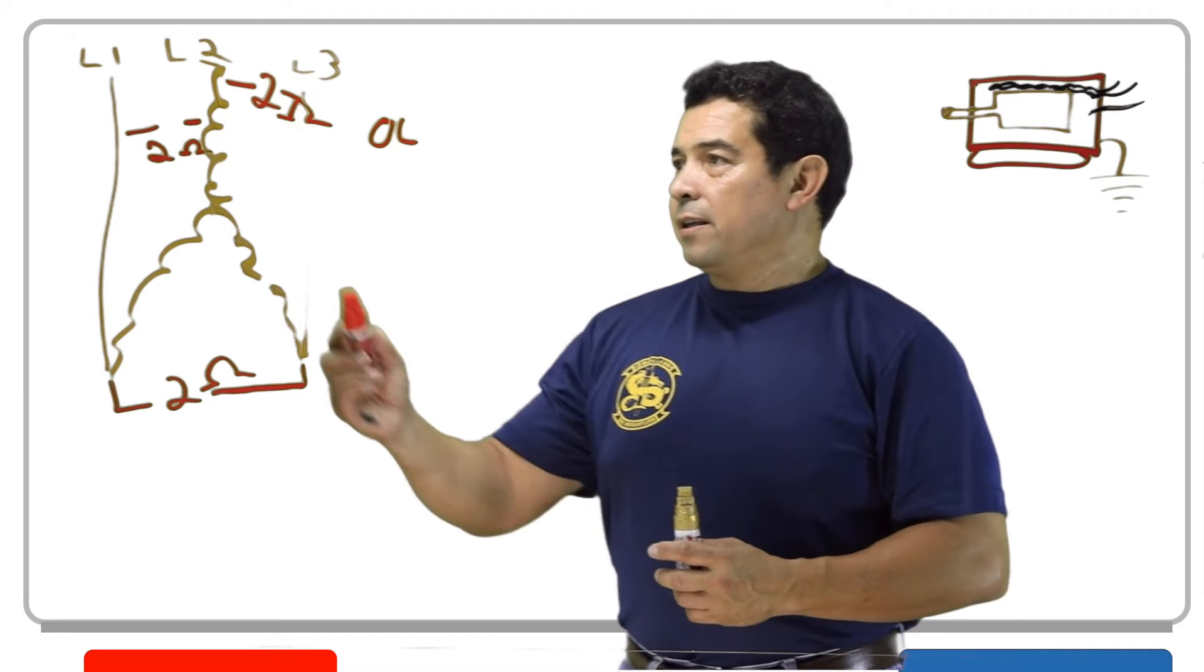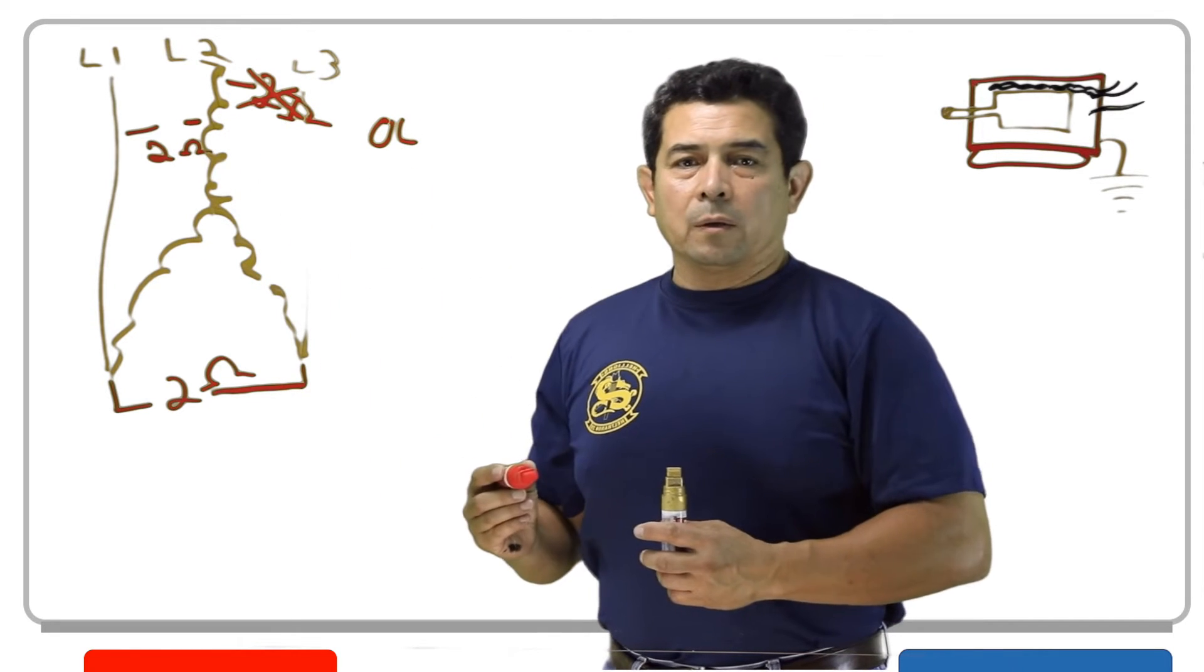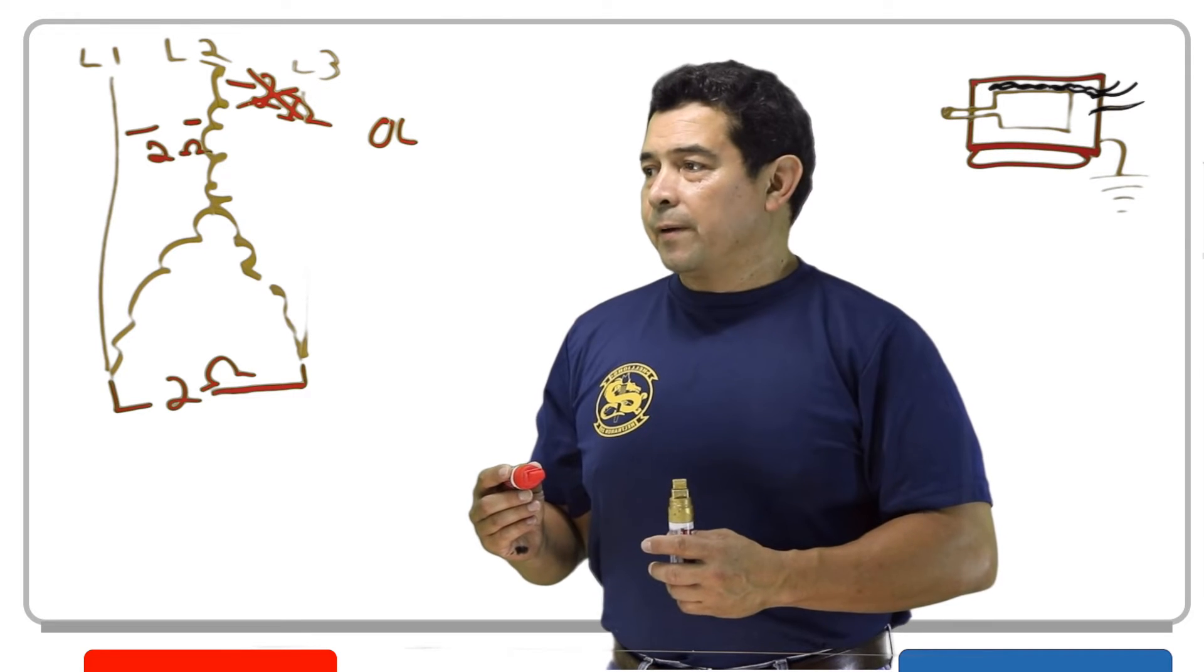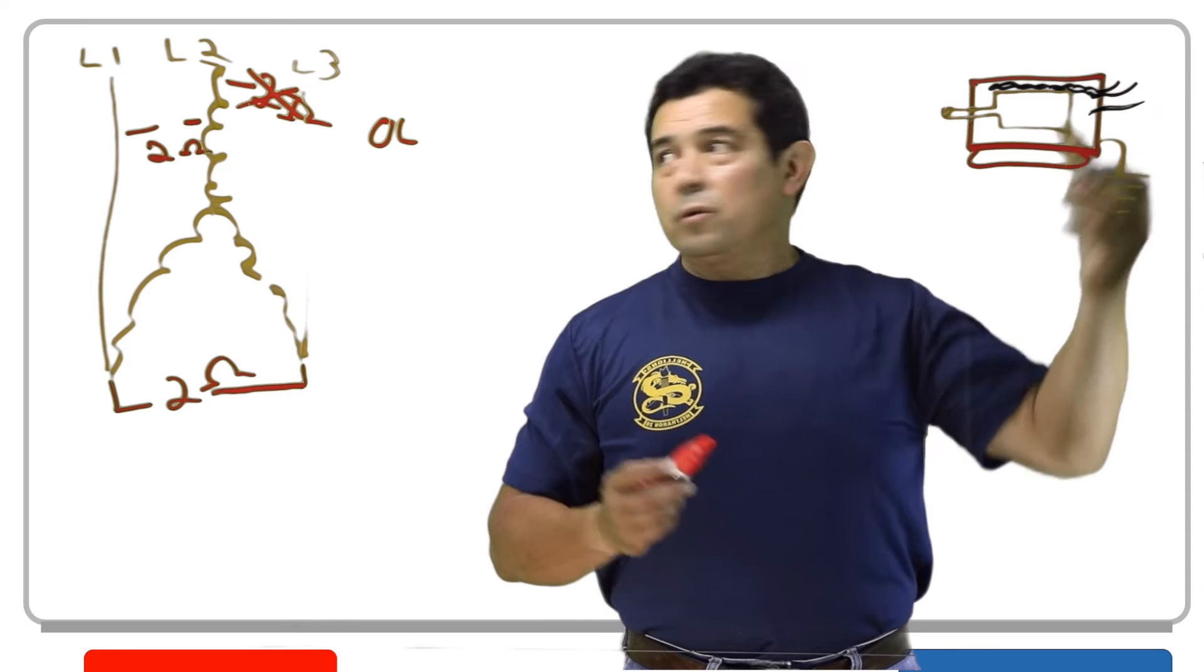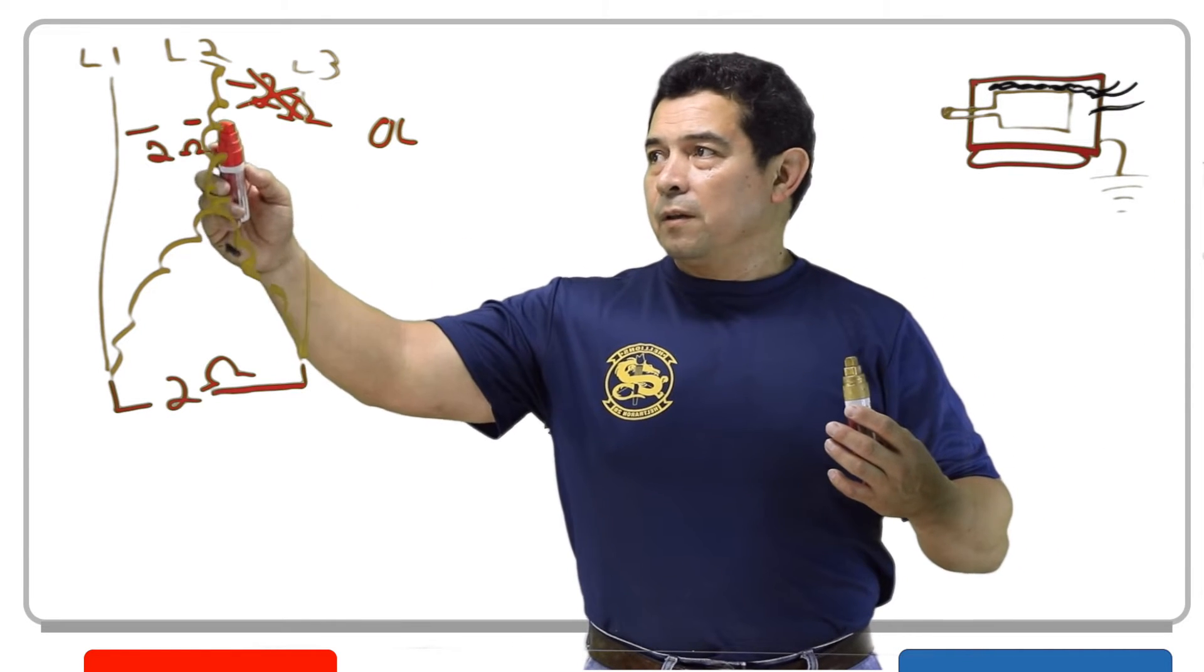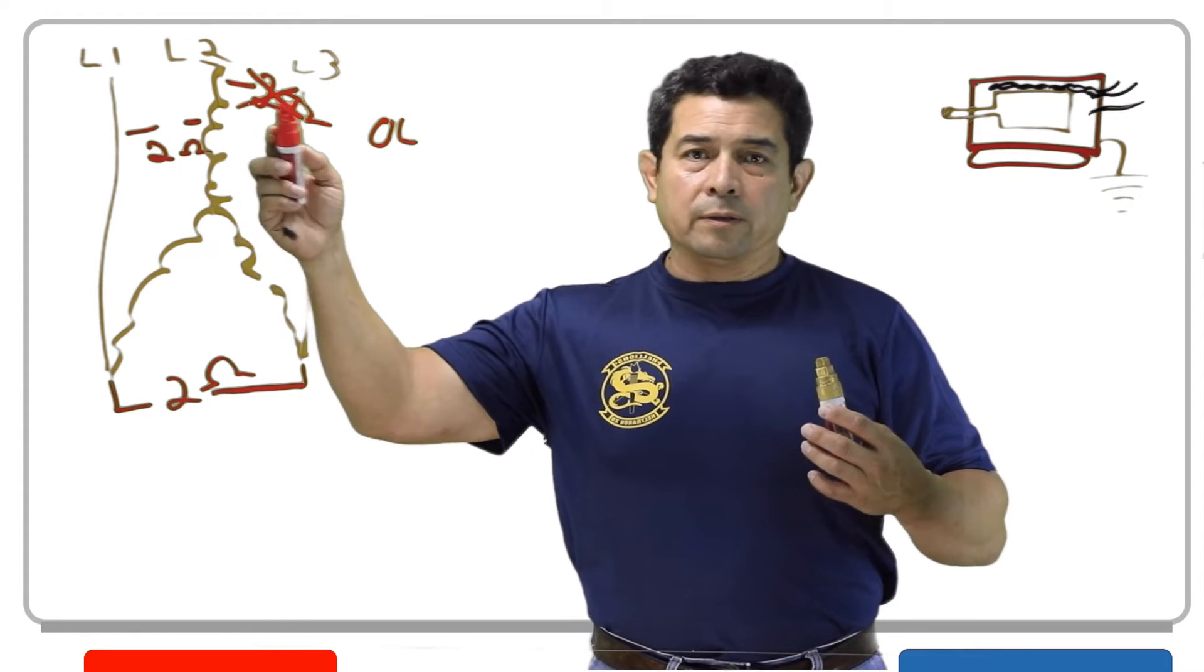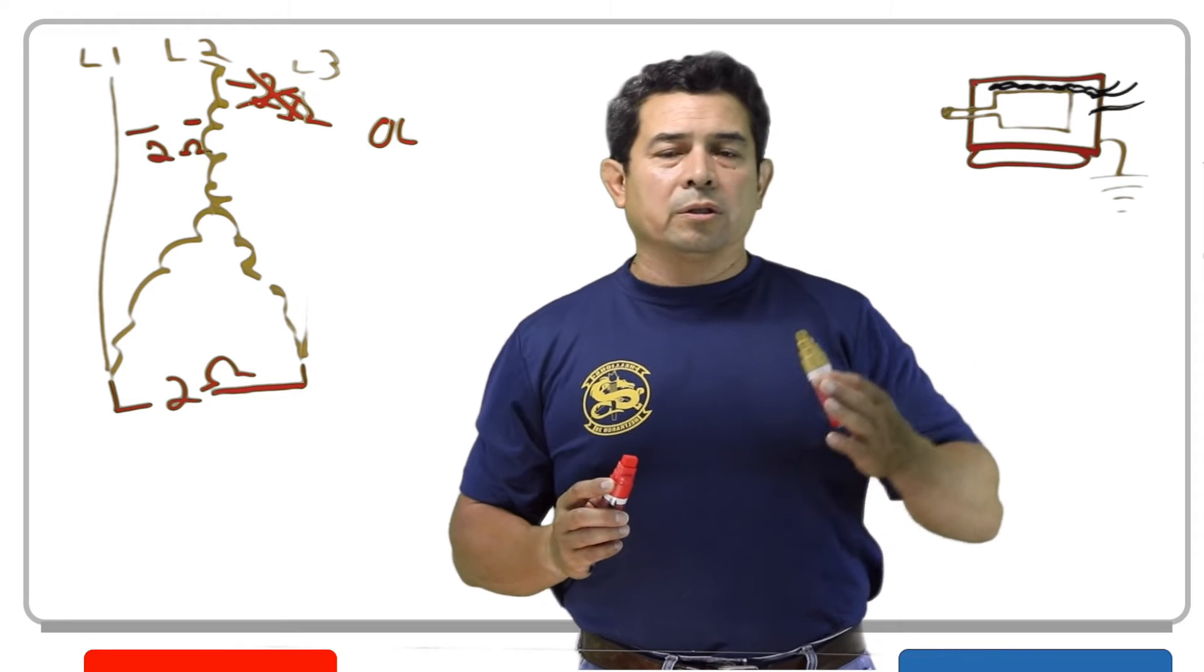But again, like I said, here, you would not get the two ohms. You would get OL on your meter. Now, the other thing is that when you check from this line to this line, you should have a reading. This one to that, you should have a reading. From L3 to L1, you should have a reading, and all the readings should be the same.